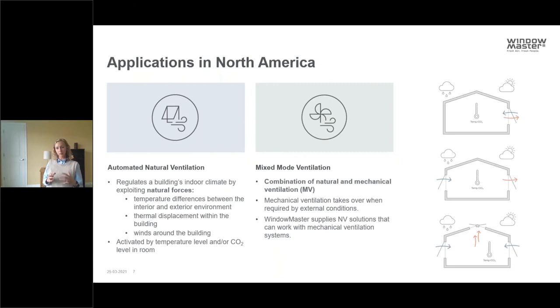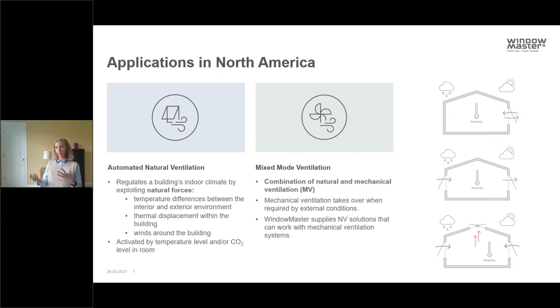In North America, window automation is typically used for natural ventilation — using the outside environment and bringing it into a built environment, either through simple open/close with a keypad or using sensors and algorithms to bring outside air in intelligently. Mixed mode, or hybrid ventilation, means using natural ventilation at certain times of the year and mechanical systems at other times. These are great solutions where window actuators play a key role.